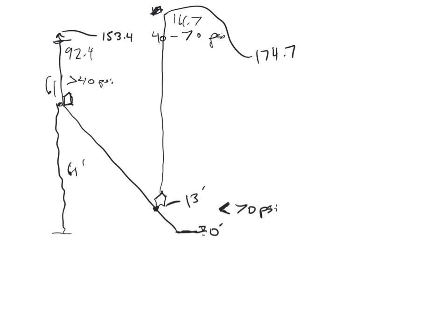Now, there's a little bit more to it because there's head losses between the tower and these houses. You're going to let the model figure out what those head losses are, but this should at least give you a band within which to design your water tower. Depending on where you place it, it's going to be a different height, but the water level in the tank still needs to fall in that elevation band.